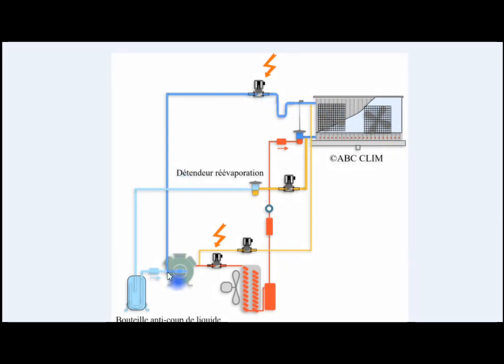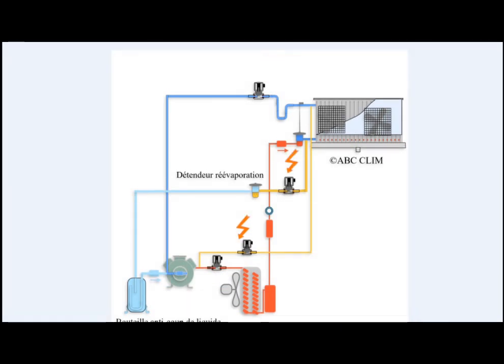Here, the gas cannot come back because we have a check valve. Now we want to defrost the evaporator. So we de-energize these two electric valves and energize these two electric valves here and here.